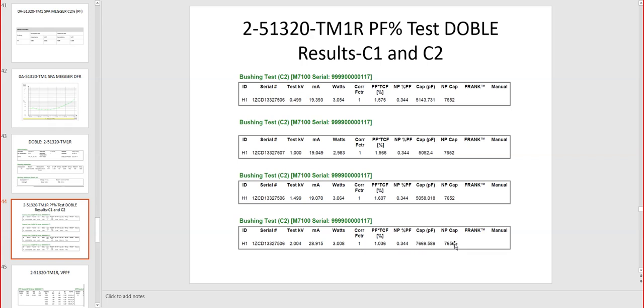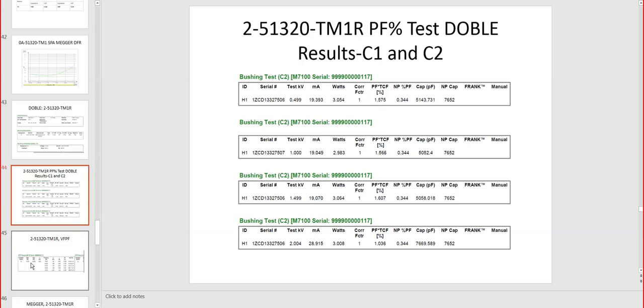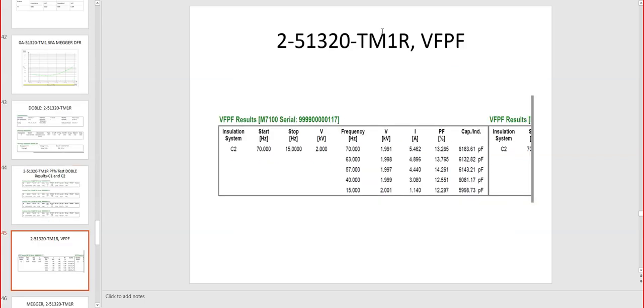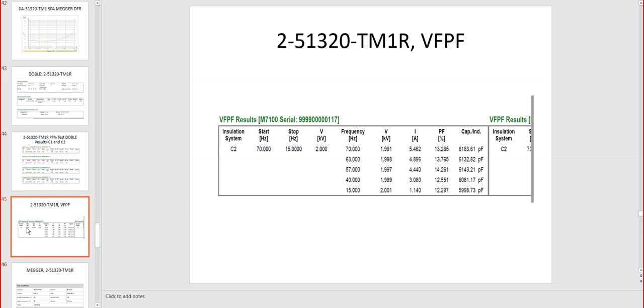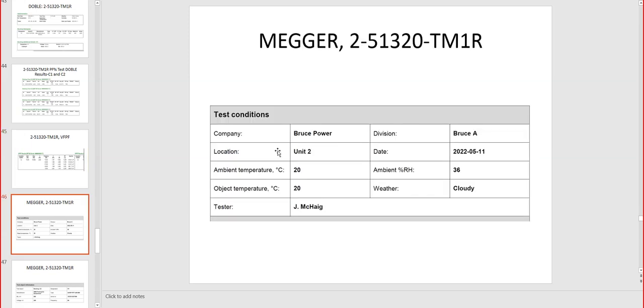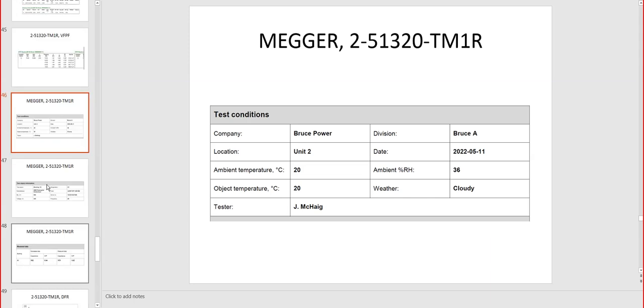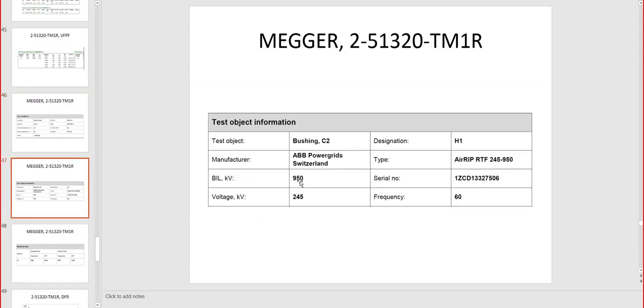And this is the capacitance that was read and the power factor for different frequency. And then we got the transformer frequency response for 15, 40, 57, 63 and 70 at 2 kilovolts, and this is the power factor that we read here on this transformer. And definitely these are the Bruce A unit 2 results from the Megger.